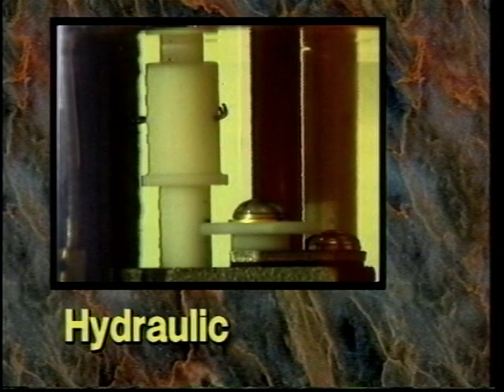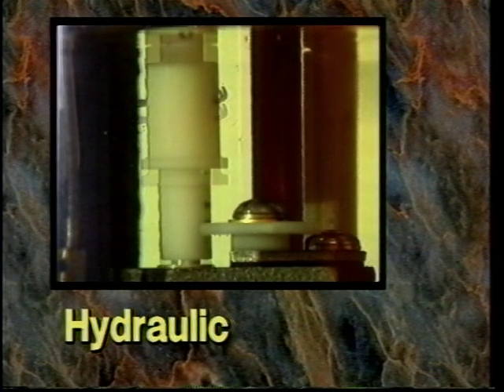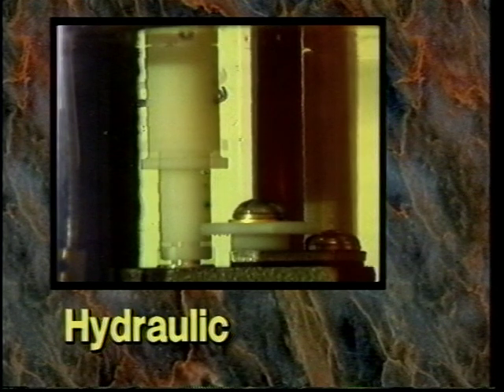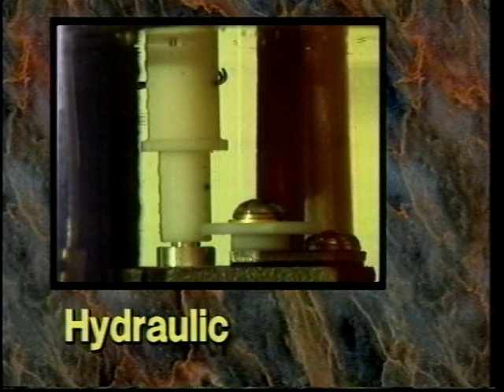Hydraulic type is an oil pump attached to the recloser plunger which raises a trip piston a certain distance with each operation of the recloser. This trip piston establishes the sequence of fast and delayed tripping operations and eventually locks the recloser open.